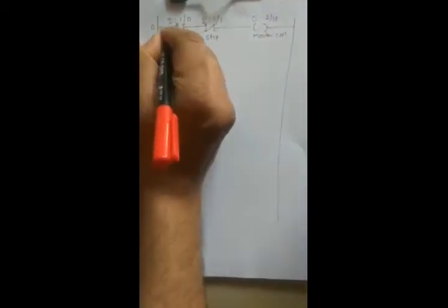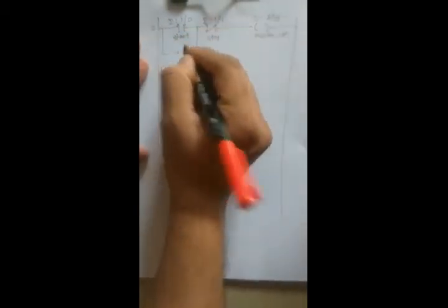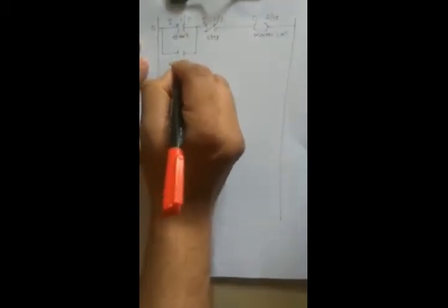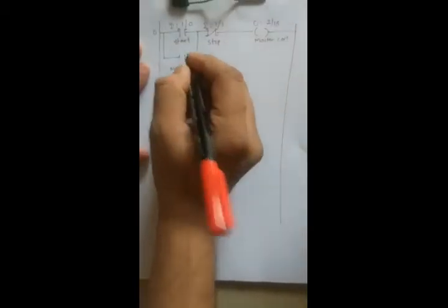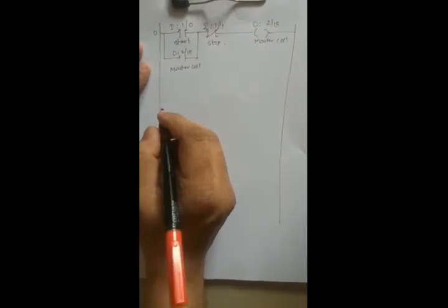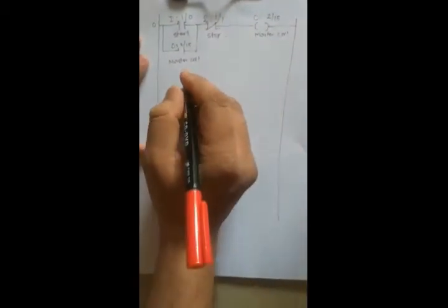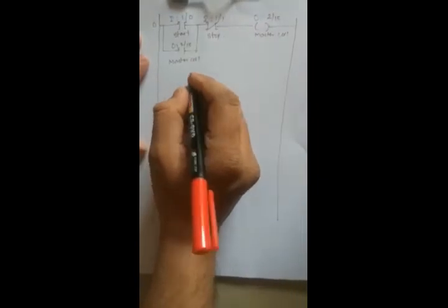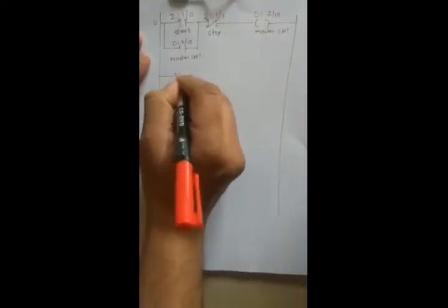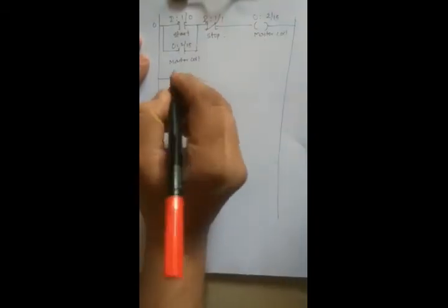Again we are using one latch contact over here, which is to be interlinked with the master coil. So write down the master coil over here and its respective address O:2/15. Now in order to turn on outputs 0 and 1, we will take the input from the master coil. Whenever this master coil becomes true, this contact will also become true.